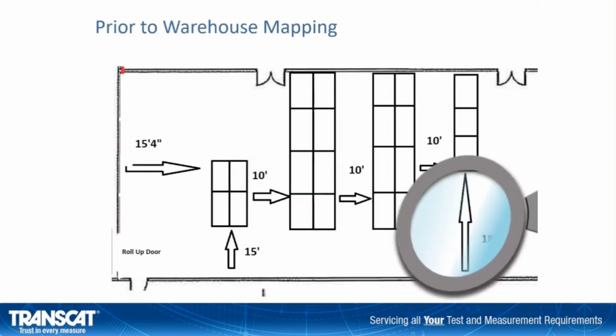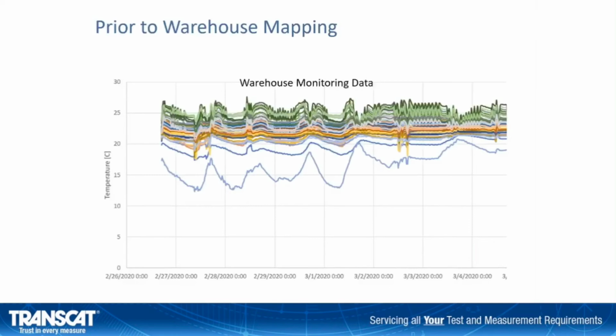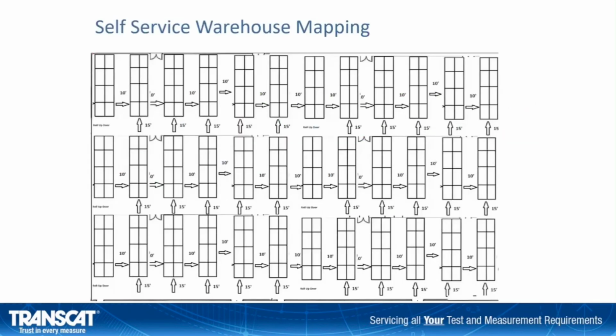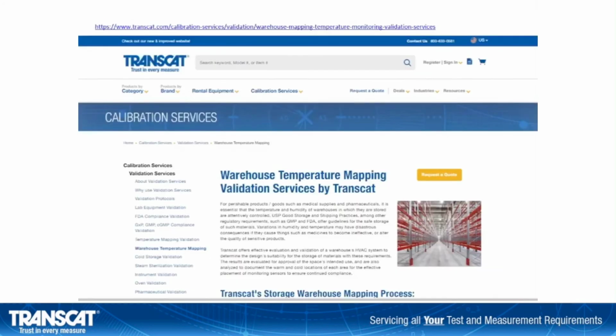Avoiding deviations by identifying and correcting potential problems before the qualification study is the best course of action. We recommend a visual inspection of the warehouse to identify potential areas of concern, and auditing historical monitoring data, as this could help to eliminate potential deviations that result from excursions. If your situation involves a very large warehouse or storage space, warehouses can be sectioned off and mapped in phases.